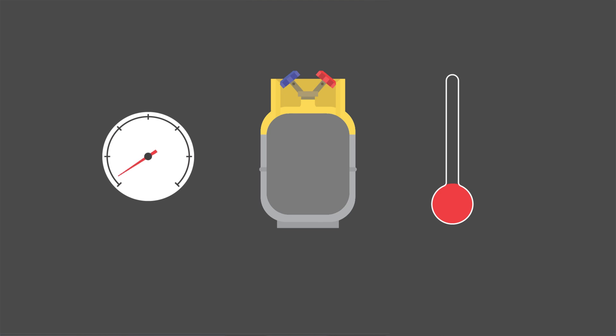Since the pressure of a refrigerant is directly affected by temperature, keeping the cylinder temperature as low as possible reduces the pressures the recovery machine has to work against, which, in turn, speeds up recovery as a whole.